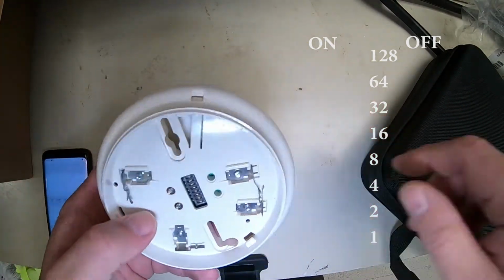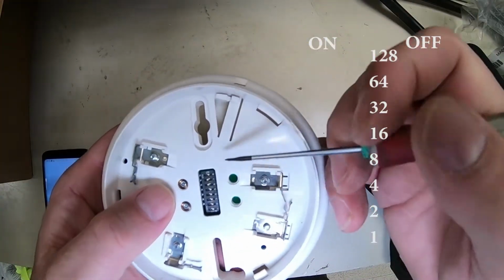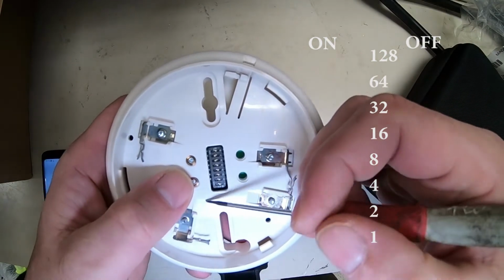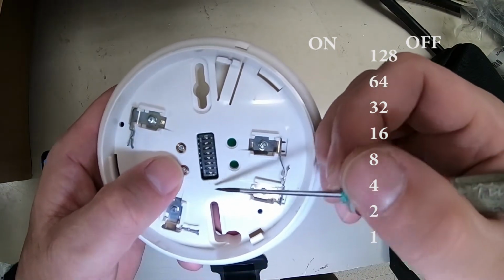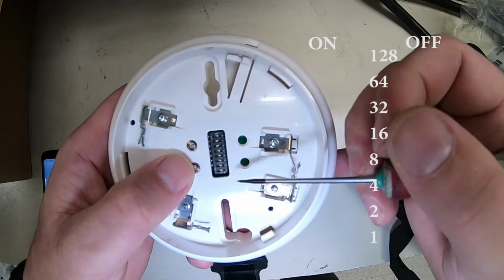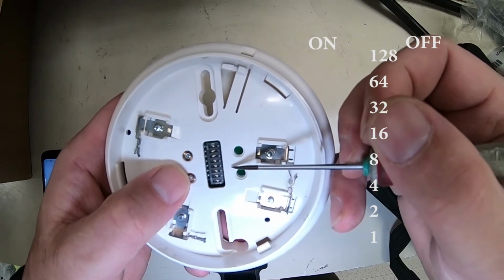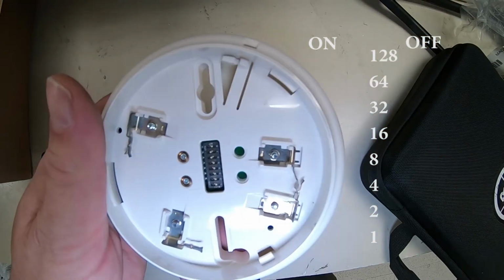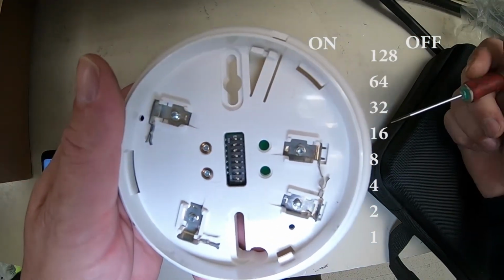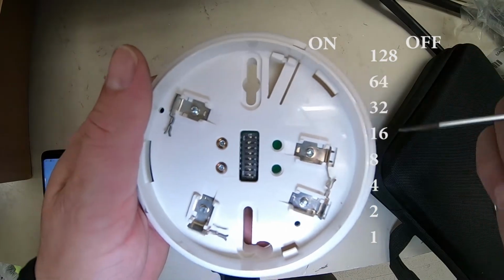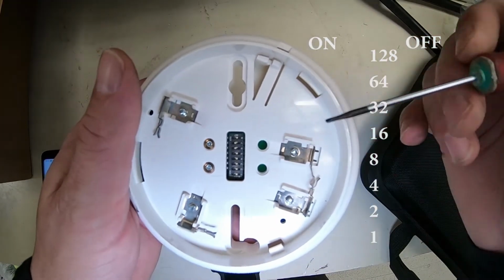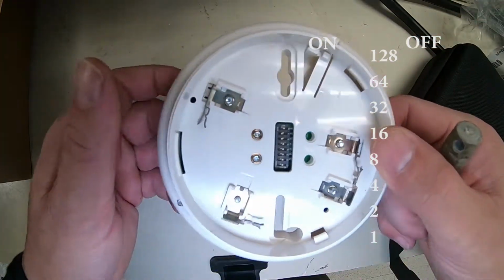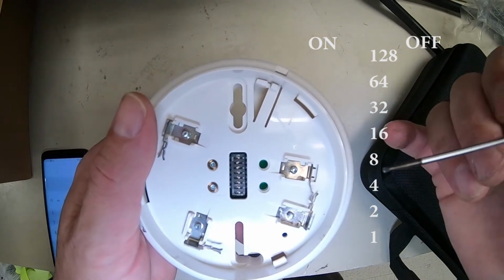Alright, to set the address on these devices is quite simple. You have switches from off to on, and on one side is off, obviously the other side's on. And you have 1, 2, 4, 8, 16, 32, 64, 128. Now these numbers are in an obvious sequence. So by turning these switches on and off, we'll actually map the address into this base.